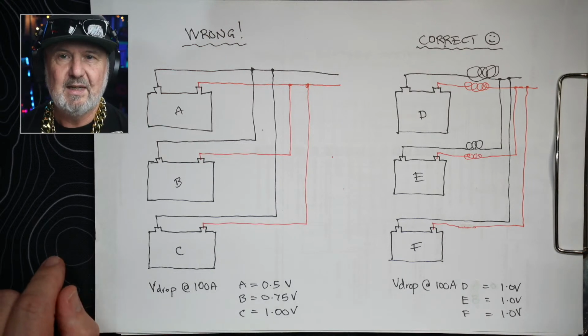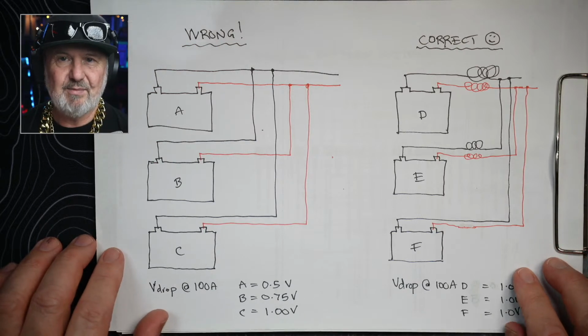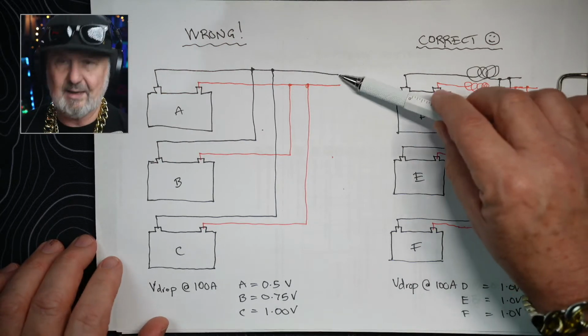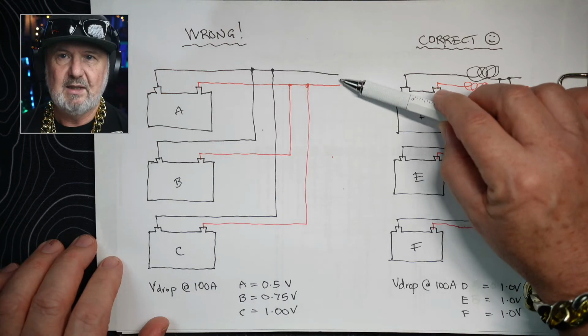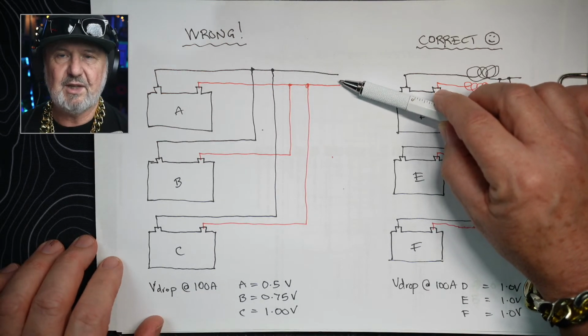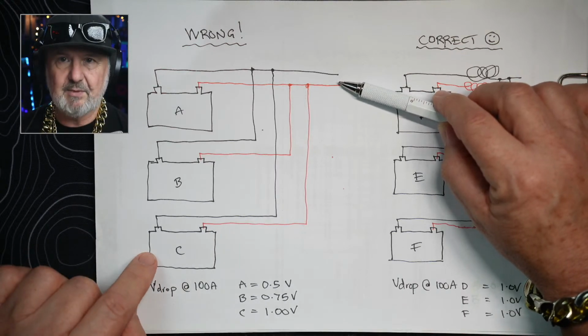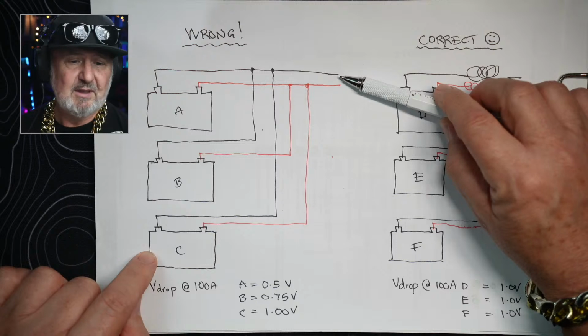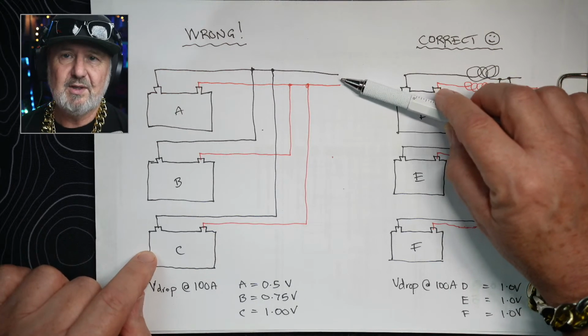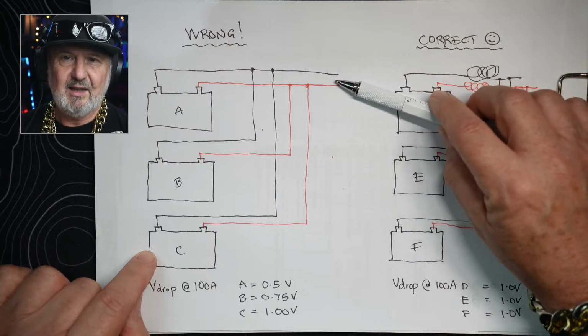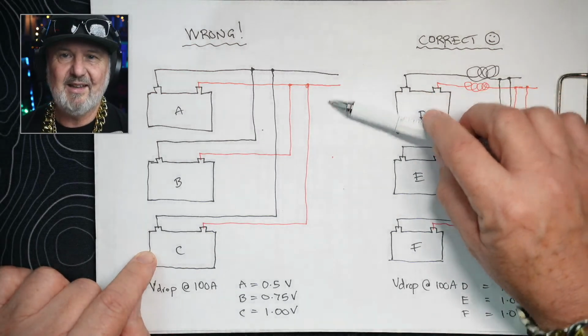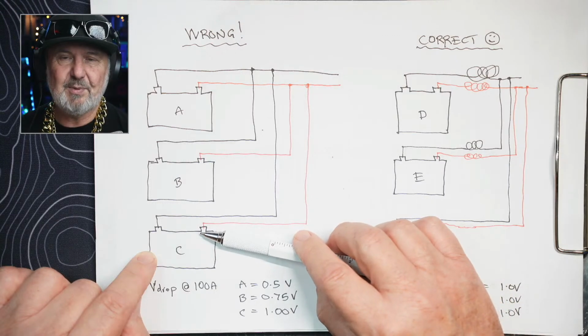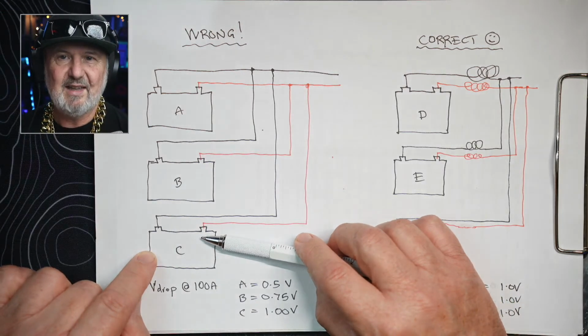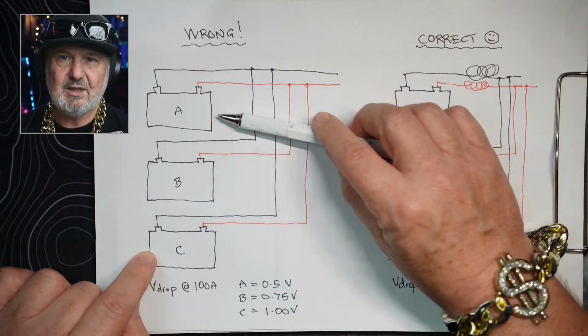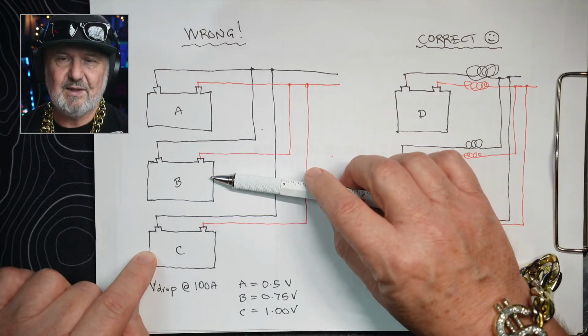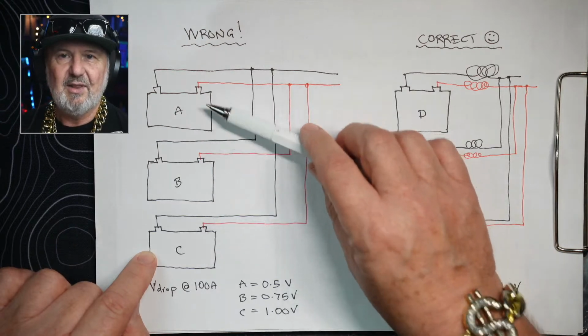Now, why is this a problem? Well, the PCE, which is trying to manage these batteries, which is connected up here, can only see the voltage at this point. And so if it's trying to reach a target voltage of, say, for a lithium-ion battery, 56 point something, 56.2, it depends on the chemistry of course, volts, and it's pumping 100 amps in, it can't see that the voltage drop here is quite severe. So this battery is not getting that target voltage. Effectively, this one gets charged first, this one doesn't get fully charged, and this one's quite a bit down. So that is pretty important.